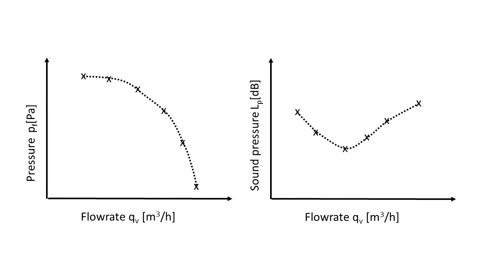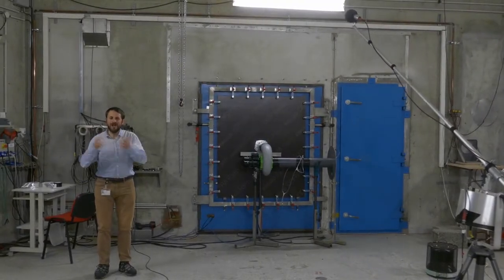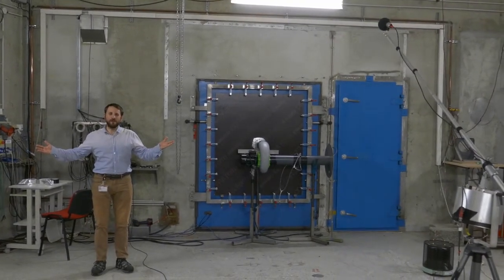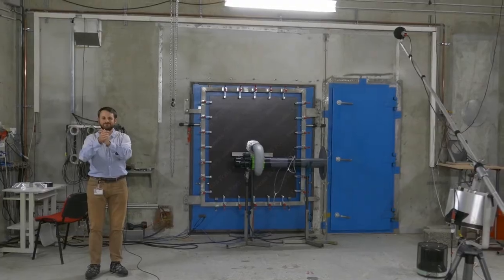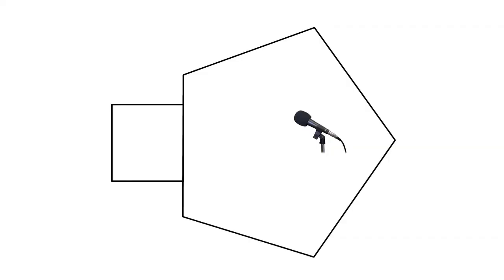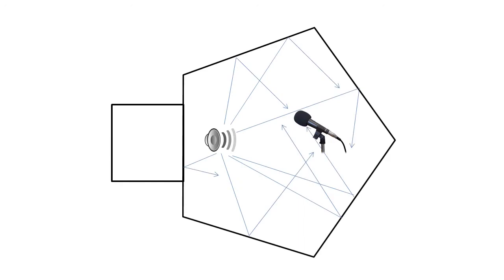So, what's a reverberant room? Welcome to a double reverberant room! Inside each room, most of the noise is reflected, but the noise field is uniform. This is the opposite of an anechoic room, where all the noise is absorbed. We install the fan between both rooms and we measure the pressure and the noise in each room.